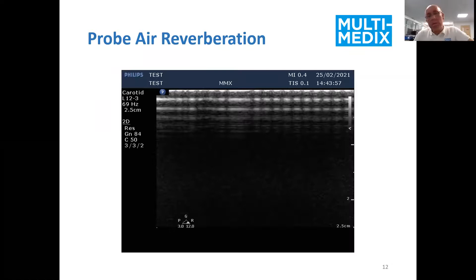And that's a topic that we're going to talk about more on our second webinar on the 15th of April, where we're going to teach you, if you're out in the field and you don't have a FirstCall available, how with the use of a specially designed test tool and a protocol that allows us to optimize the scanner settings, we can identify the equivalent of that FirstCall test result. We may not see the full root diagnostics, but we can get the same understanding of defects on the probe very quickly, very easily, in less than 5 minutes, with just the use of a specialist small test tool, which looks like this.